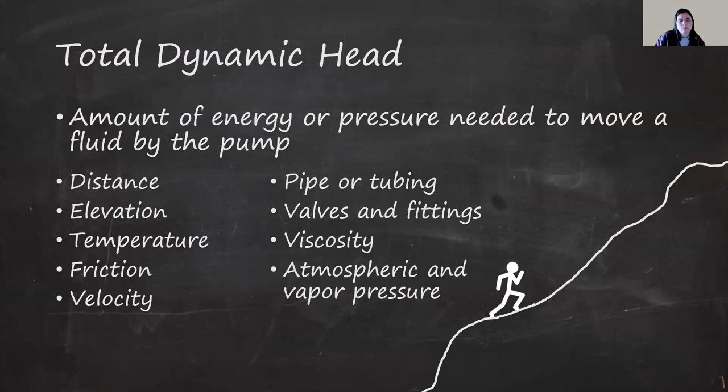Depending upon the pump manufacturer, this energy can be expressed in a variety of ways. Typically, it's called head and is annotated in feet, but may also be seen in terms of discharge, lift, suction, and pressure. A useful conversion factor is 1 psi is equivalent to 2.31 feet of head.